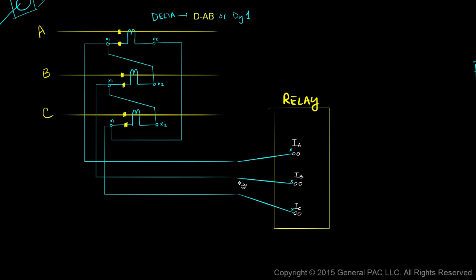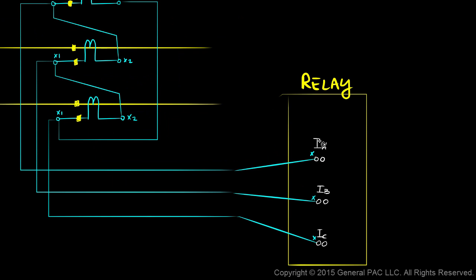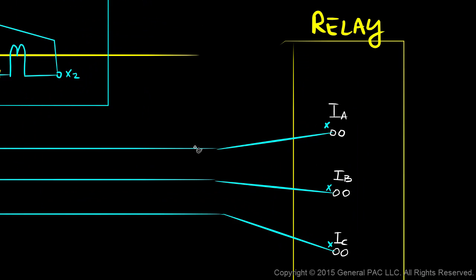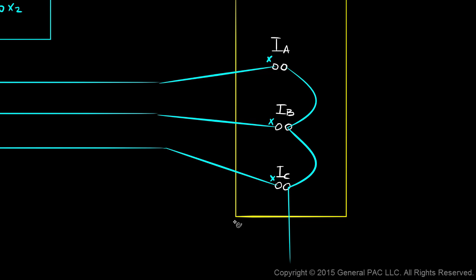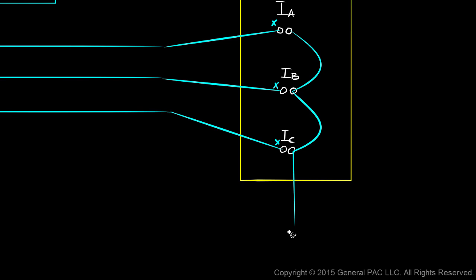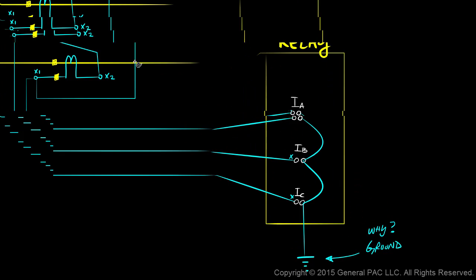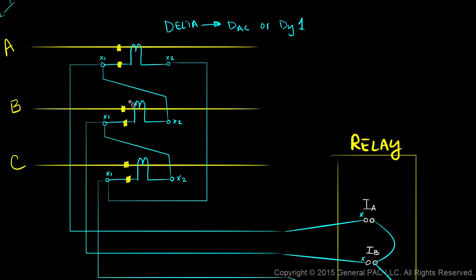Next, we connect the non-polarity side of our relay input terminals together: the non-polarity side of input terminal A is jumpered to the non-polarity side of input terminal B, which is jumpered to the non-polarity side of input terminal C, and that is grounded. Why we ground this side is a discussion for a different module, but for now let's focus on the current flow for our delta-connected CTs.